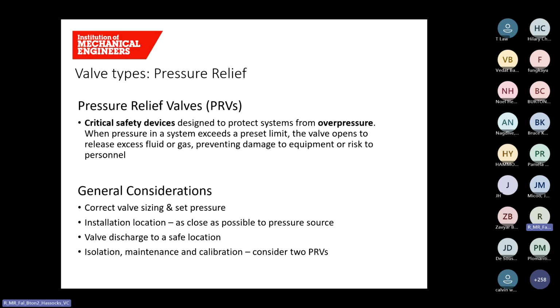Generally, isolation valves are discouraged, and that's because they introduce a risk of unintentionally blocking the only path for pressure relief. If a system experiences overpressure whilst the relief path is isolated, it can lead to catastrophic failure. That said, there are occasions where isolation is unavoidable, such as calibration or maintenance, so it's essential to install a second pressure relief valve.